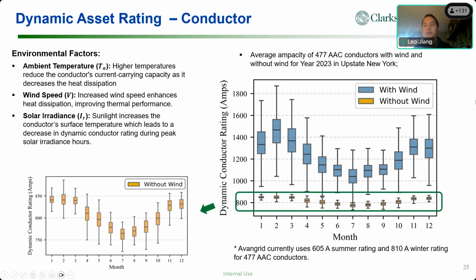We also did that for conductors. I think dynamic line rating has been more demonstrated on the transmission network. But if you look at the same principle for the conductors, there are ambient temperature, wind speed, and solar irradiance. They all impact the thermodynamics. In the end, the temperature gain of your conductors will limit their thermal capacity.